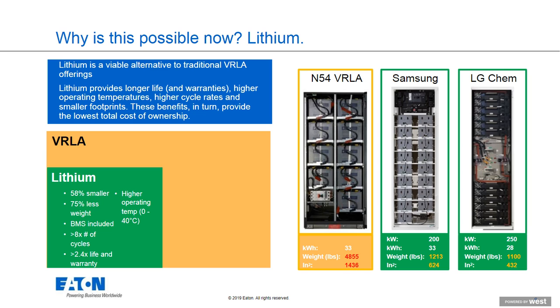One challenge with traditional UPS batteries is that after 200 to 500 charge-discharge cycles in just a few years, the battery is worn out. The difference with lithium batteries is the high cycle count capability, which allows the battery to be charged and discharged to various depths over and over again and still maintain the long service life the customer requires for this large investment.